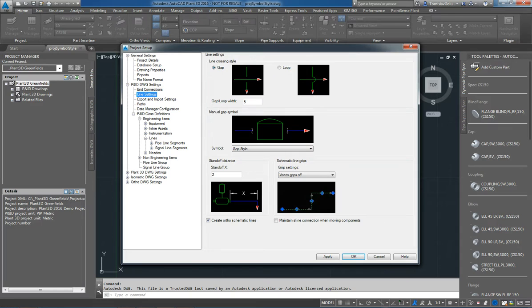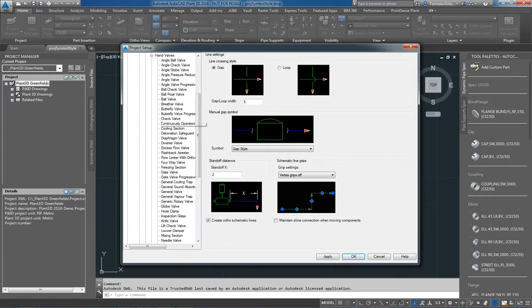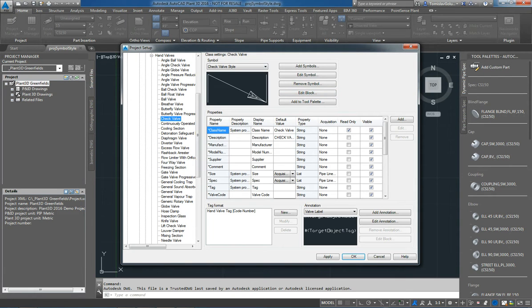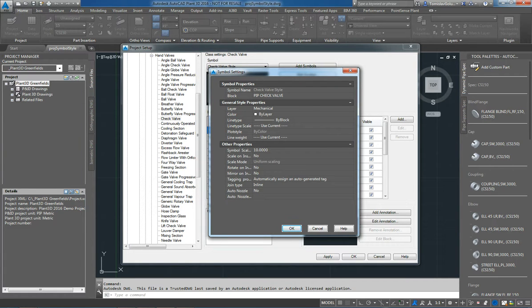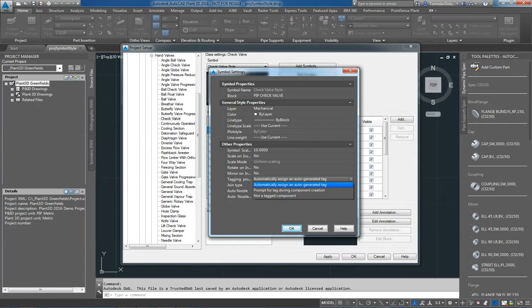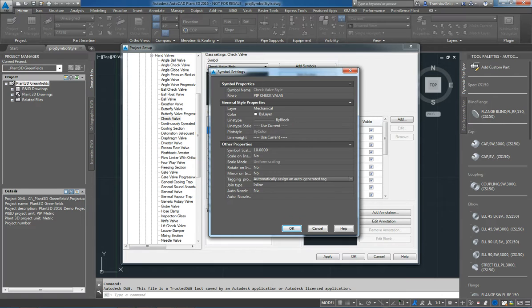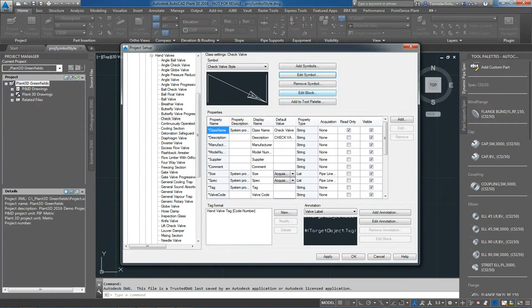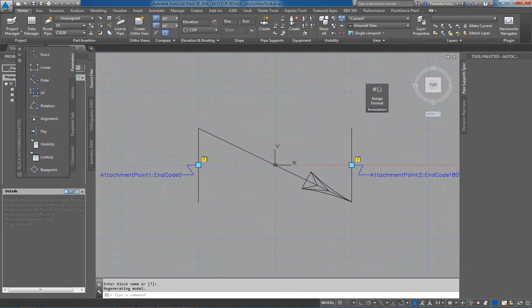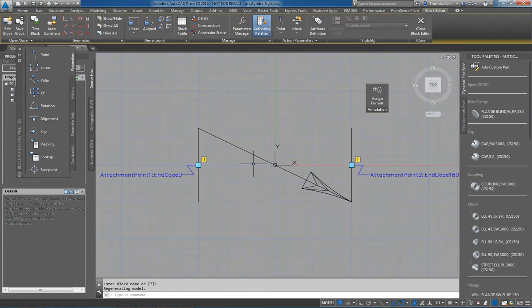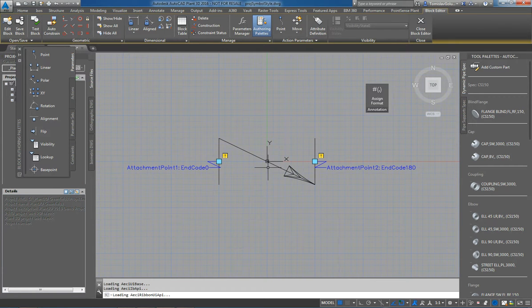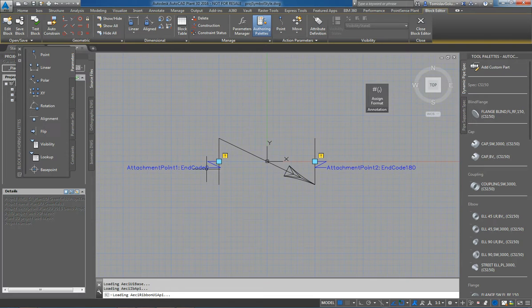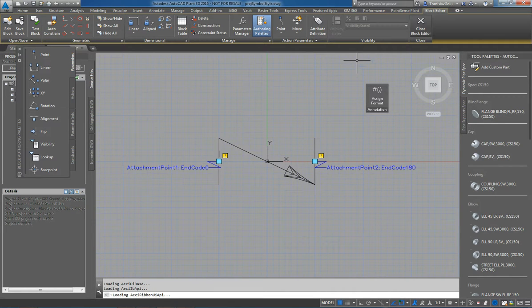A few settings for the line settings, and then the main thing I really want to touch base on is things like these P&ID class definitions. So if I go through and have a look at something like the check valve style, if I click on edit symbol, it takes me to a new dialog where I can modify the layer, the color, and if it was a line, I've got line type scales obviously, and I've also got symbol scale. Being a valve, I can tell it to automatically generate a tag, maybe I don't want to tag it, or maybe I want it to prompt for a tag as well. And then if I want to edit the block itself, I just click on edit block and it takes me into the block editor again. I can adjust the size of it, how big it is, whether the arrowheads are going to be filled or open, and adding these EndCodes in. So these are important for when you're placing it, we have an EndCode0 being the beginning spot and EndCode180 being directly opposite it.